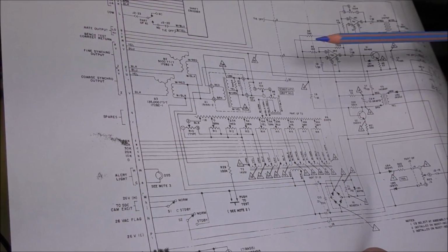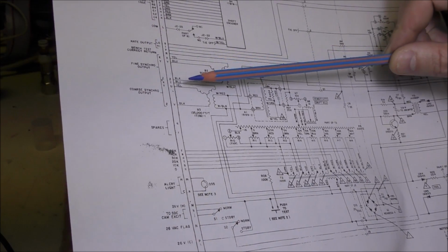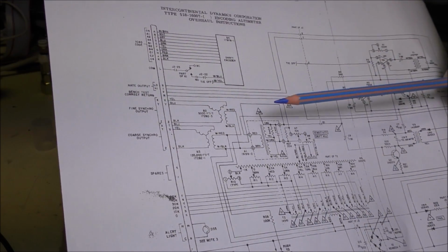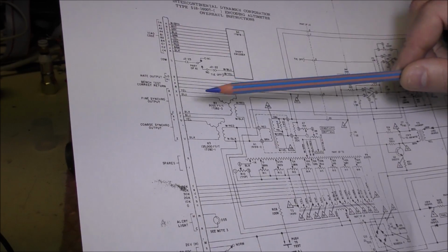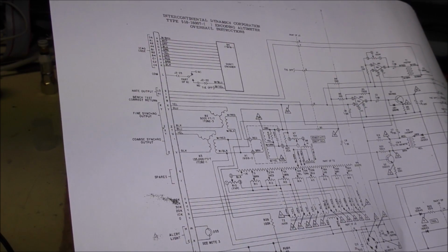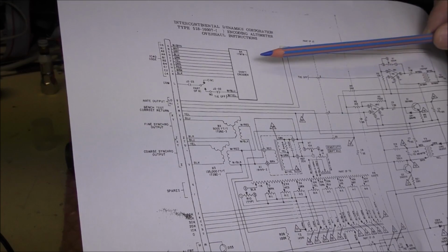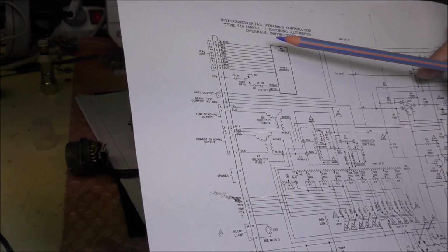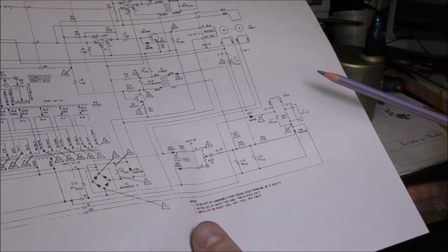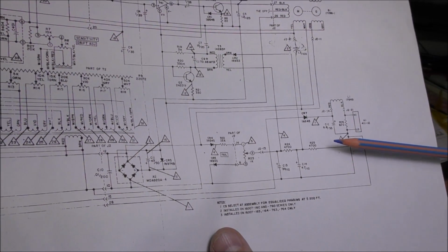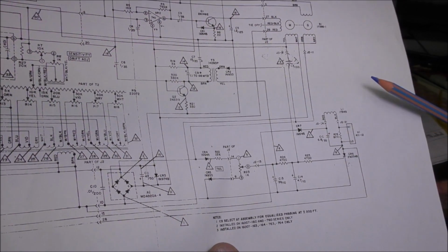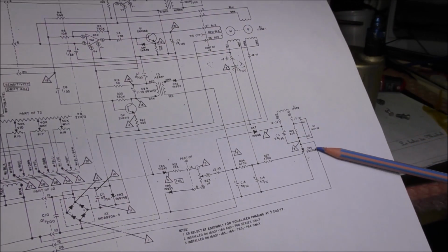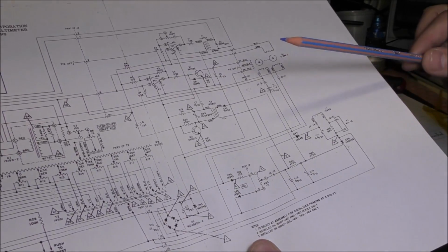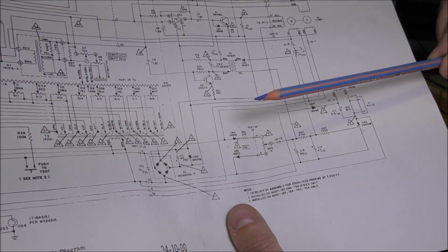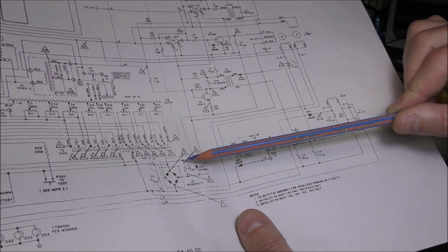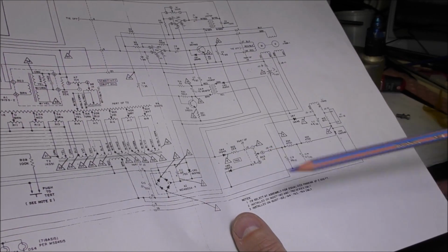And we can see also we have these two synchros, the fine and the coarse synchro for the output measurement, and you can connect this to another indicator or something else. So we have the encoder here, so we'll be able also to test this thing. And there is also this circuit which permits to activate the flag, so it is actually identical to the circuit also of the Collins instrument. So there is this SCR. So there are different conditions. So the first condition is the value of the 26 volt AC voltage. The voltage is sensed between these lines using this adjustment.